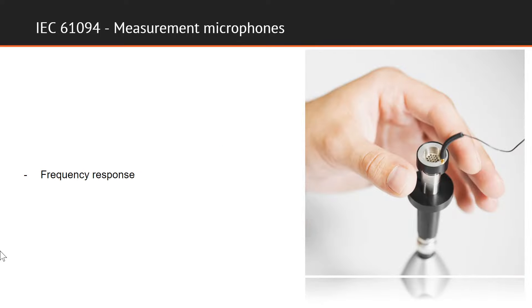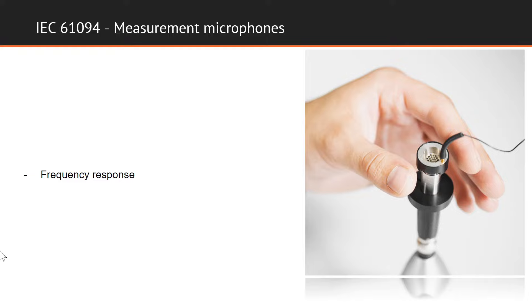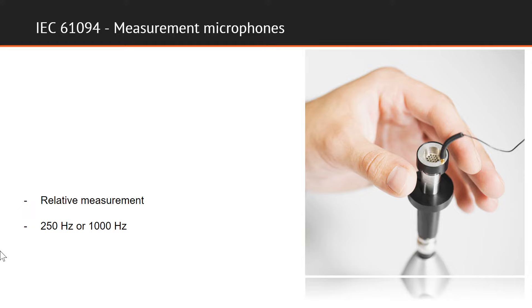In addition to measuring sensitivity, the frequency response is determined using an electrostatic actuator. This is a widely used tool that can simulate a constant sound pressure on the diaphragm of the microphone, and it can simulate this constant pressure over a wide frequency range. The actuator measurement is a relative measurement, and the results are normalized at the sensitivity measurement frequencies, which are also called reference frequencies, and they are again 250 Hz or 1 kHz.